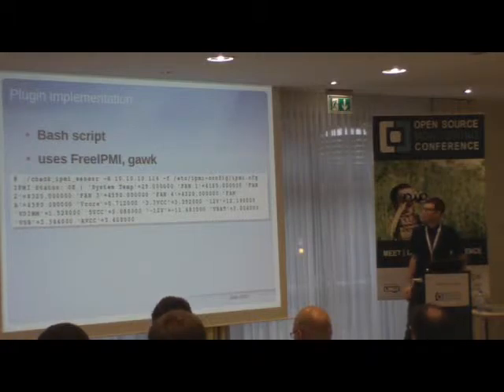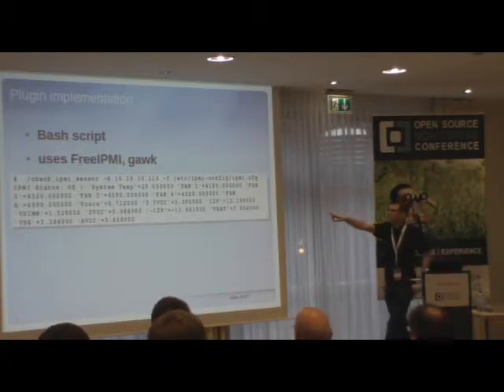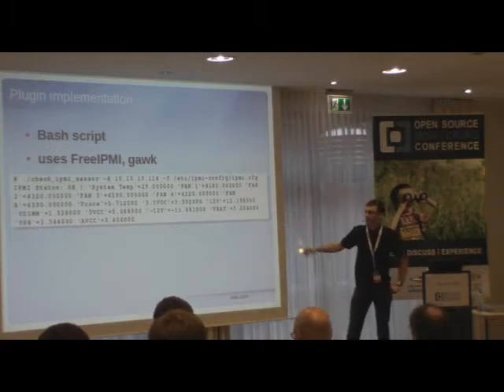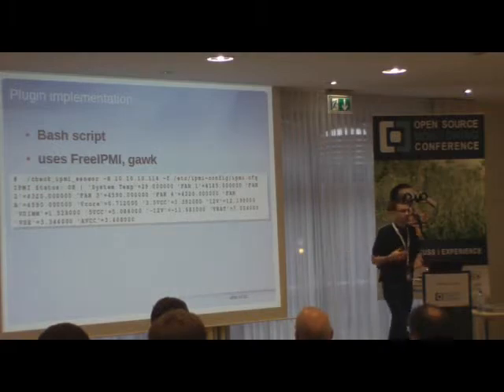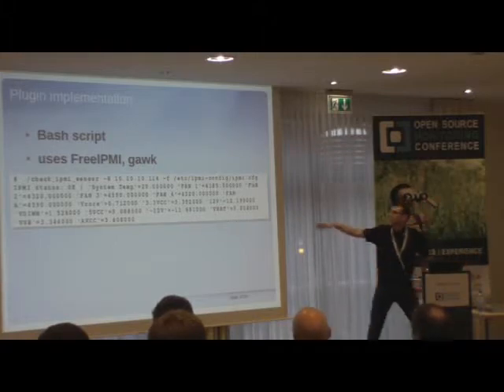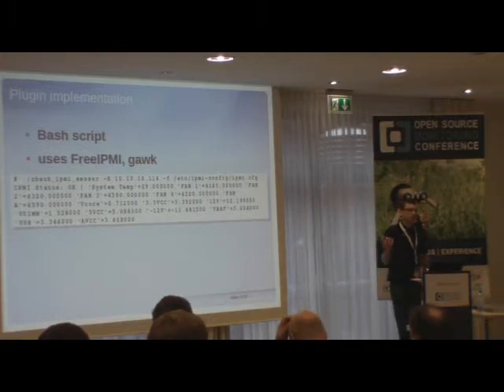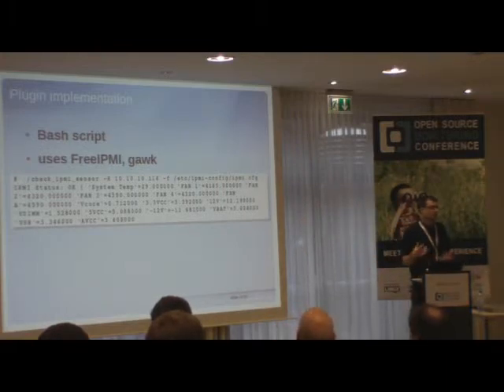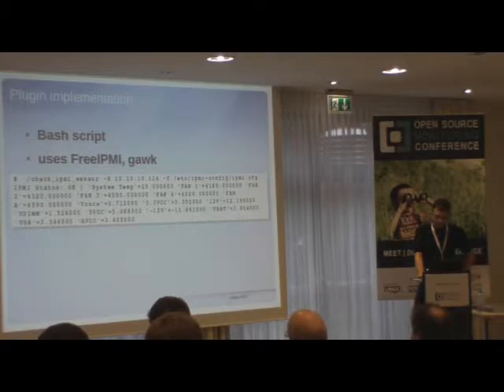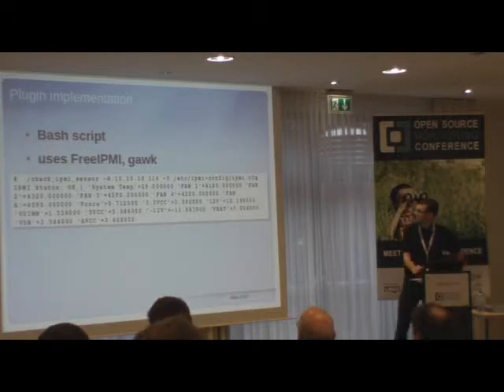Then we get the output, as defined by the Nagios plugin development guidelines. We have the status information, then the pipe symbol, and a bunch of performance data — and of course the return code indicating whether it's okay, warning, or critical. In this case we see all sensors are okay and we get values for all threshold-based sensors with analog readings, which we can use for PNP for Nagios, or graphing tools.